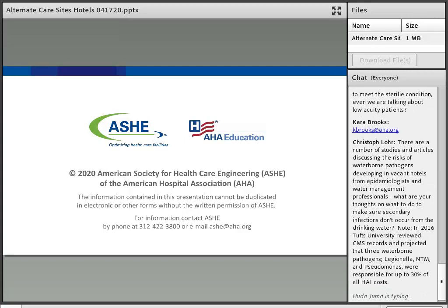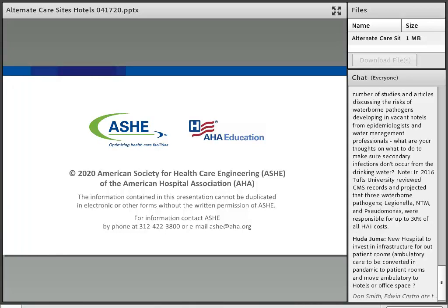Great. Could a typical hotel, not a high-end one in a city, but a typical plain hotel be converted? There are a lot more of those choices around the U.S. rather than the high-end hotels. Do you have thoughts on that? Yeah, I think the approach is the same. If you're referring to the Hampton Inns or the other 3-4 story type buildings, no reason why they couldn't. Those typically have the VTACs or the PTACs, so the outside air consideration is important there, and it might impose some restrictions or limitations for air exchanges that you'd want to achieve for a healthier indoor environment. But yeah, no reason why not.